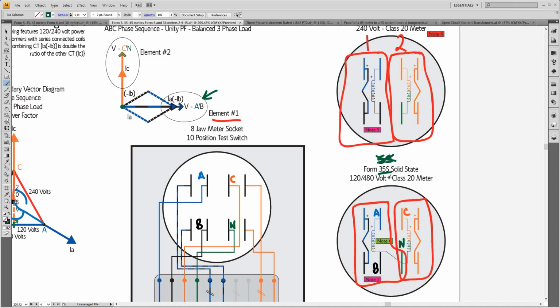It was marked as a 5. And so we had these meters installed in the field, marked as a 5, really a 35, and as the meterman would go out and do stopwatch tests as opposed to load tests from the power mate they were using, we found lots of metering errors because this marked 5S meter was not working correctly with that phase to neutral voltage across that potential coil. So ABB went back, I can't remember how long, two weeks, and says, okay, we're going to send you a new meter. We're going to label it now as the 35S, which it was all along.